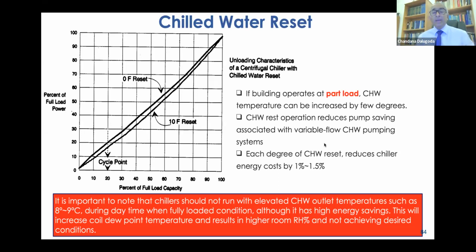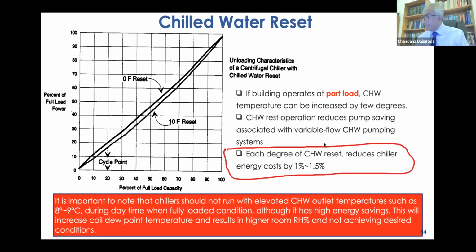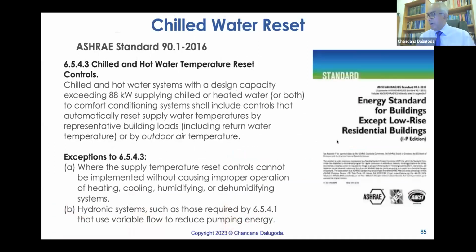So we'll have to find whether the building operates on a part load. So we need the BMS system. The important thing, each degree of chilled water reset reduces chiller energy cost by 1.5%. This is massive. But unfortunately, in Sri Lanka, our people misuse this. They put it to 10 degrees C, and there are condensation issues. Humidity is high. Then they turn back to the designer. They turn back to the installer. Big problems. Now, this has to be used in part load, significant energy saving. ASHRAE standard: any system above 88 kilowatt needs resetting.